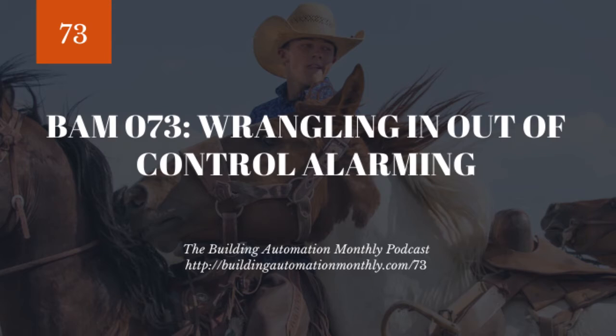So what causes out of control alarms? How do we get to this point where you have a building automation system where the alarms just never end? After all, we go through these plan processes, design processes, all these checks and steps to make sure we're not at this point. Yet so many projects, I'd argue near 99% of them, end up in a situation where all the alarms, if they even exist, are set to the same priority, they route to the same person, and no one can tell what's important and what's not important.